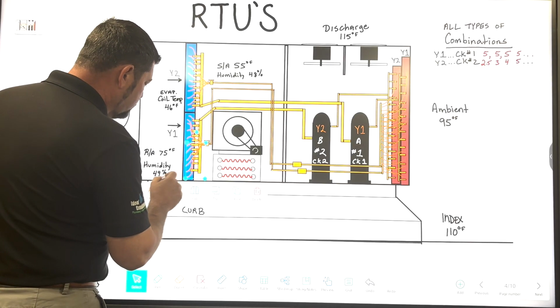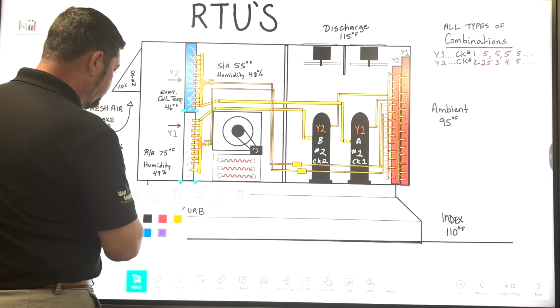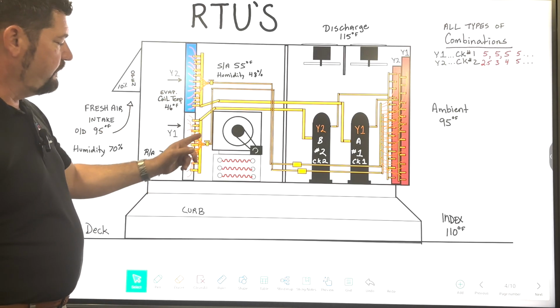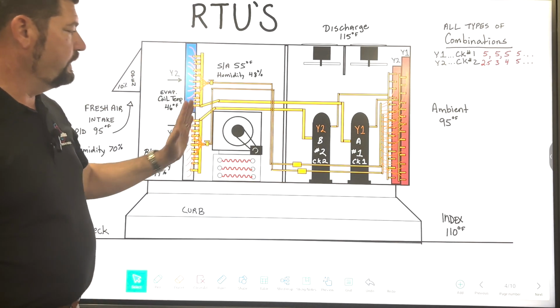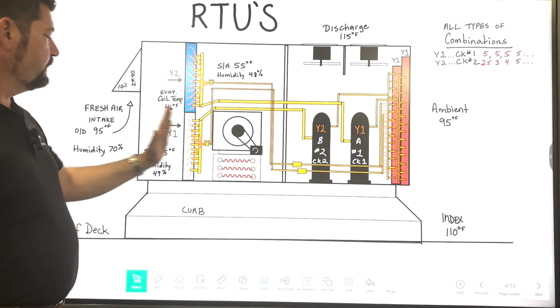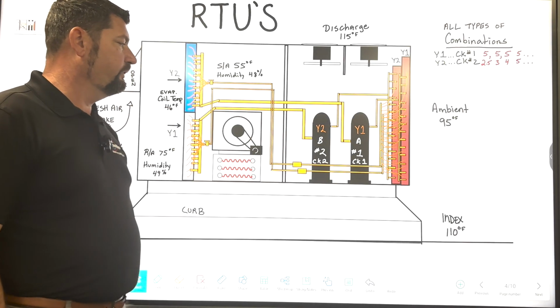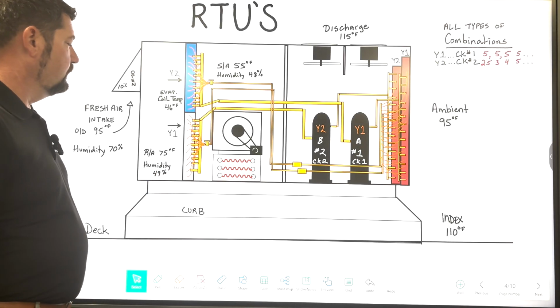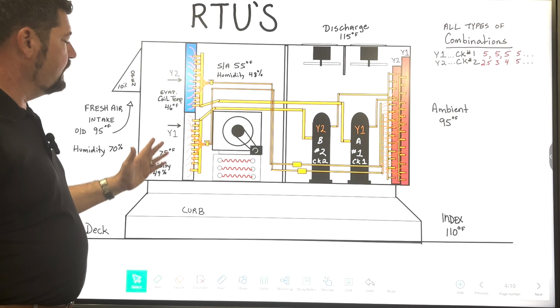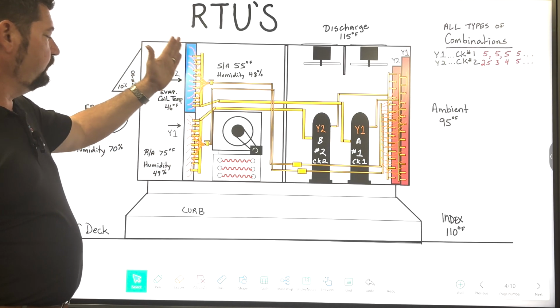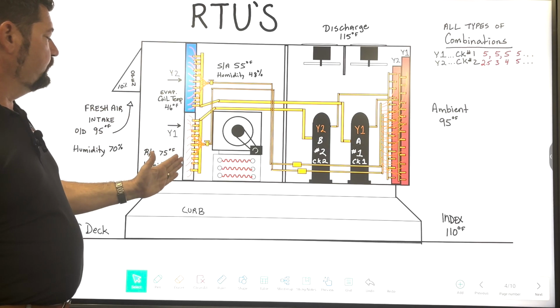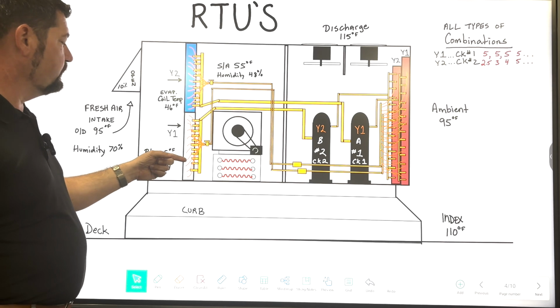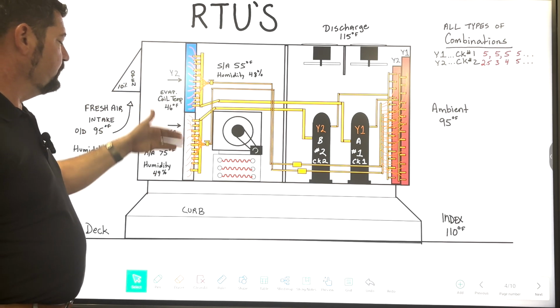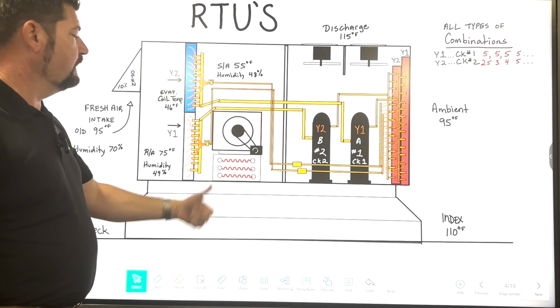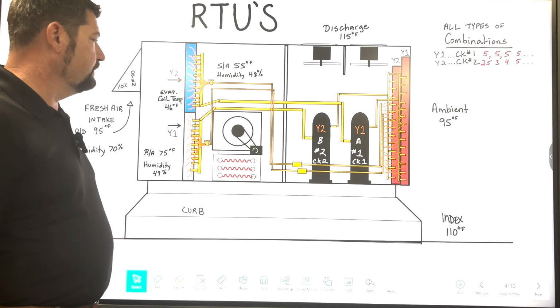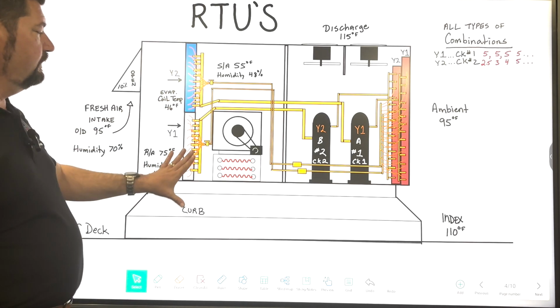Give me a second here. Oh, come on. There we go. So let's just say that coil, I'm turning it white here, because if that valve is bad, then over here we have a high head pressure. We're starving the coil of liquid refrigerant, so the returning gas is going to be at a low pressure, high subcool, high superheat situation. Not to really get into that, but if this was the case, then the water that is collected on this coil at 46 degrees will run down onto this coil, which is sitting at around room temperature, 75 degrees, and the humidity that is removed up here is just going to be added back to it, meaning you're not removing any moisture. You may be getting some of the heat out of the building, but you're not going to be getting the humidity out of the building in this situation.